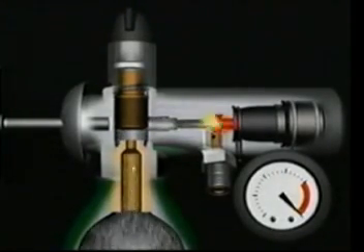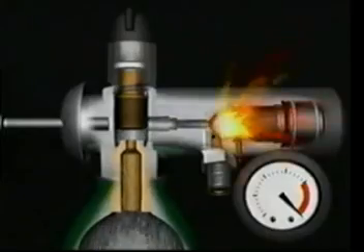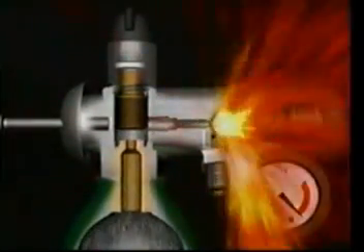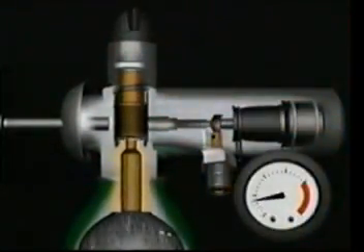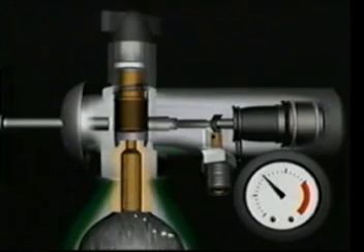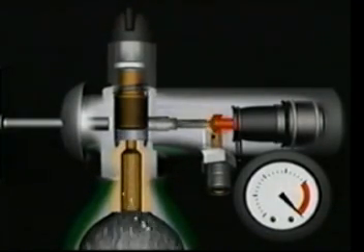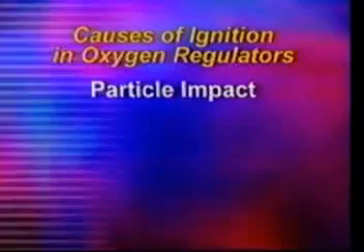When the particles hit the internal surfaces of the valve or the regulator, heat is generated. Now although these small particles wouldn't burn in air under high pressure, they can burn in oxygen, and that can ignite a fire.